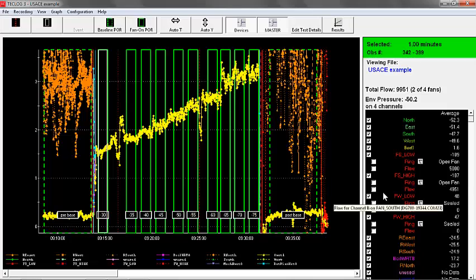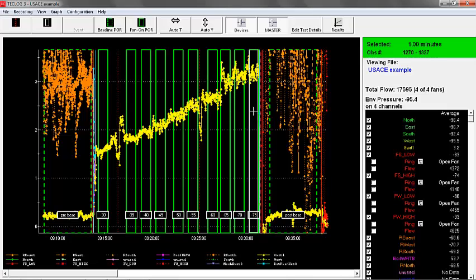So we're within 5%. We need to be within 10%, and we're within 5%. And then if we look at our highest end here at 75, we're at an induced pressure of 75 in this case, and our pressure in that space is 3.2.